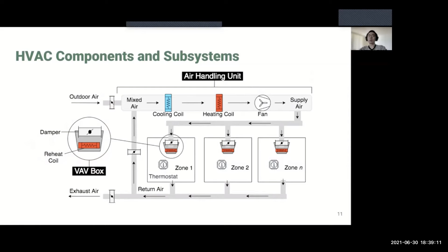This figure shows the design of the HVAC system used in our building. It consists of a centralized air handling unit that moves conditioned air through the building via a duct system. In the air handling unit, the outside air and the return air from zones are mixed together. The mixed air is then heated or cooled using one heating coil and one cooling coil to a specified temperature before it is pushed through the duct system by a fan. Variable air volume, or VAV systems, are used for controlling the amount of supply air by opening and closing a damper. A reheat coil present in the VAV box heats the supply air in the zone to the desired temperature. This allows each zone to have its own thermostat with a unique temperature preference. These VAV set points are controlled using a feedback control strategy, and the VAV reheat coils are turned off in the cooling season.